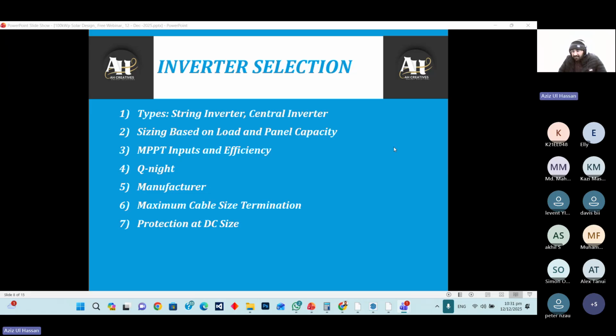Sizing is based on the load and panel capacity. We have to size our inverters on the basis of the panel capacity, the PV module current, and the inverter input current. Then the MPPT input and efficiency. The manufacturer will tell us how many MPPT trackers are installed in one inverter, how many strings can be connected to one MPPT tracker, and the efficiency is also given by the manufacturer.